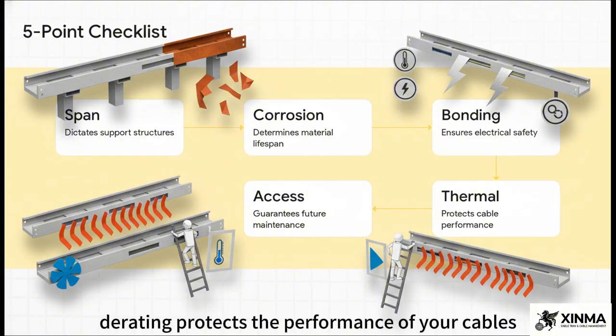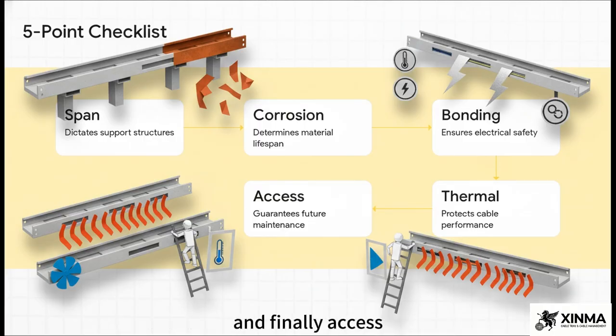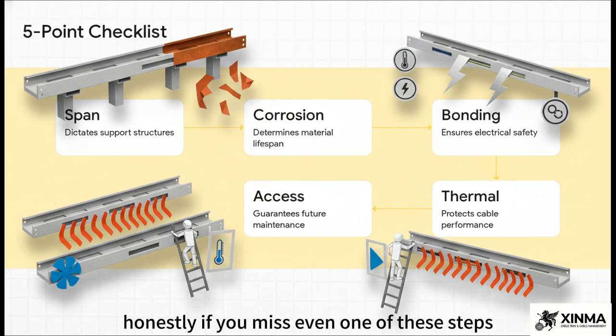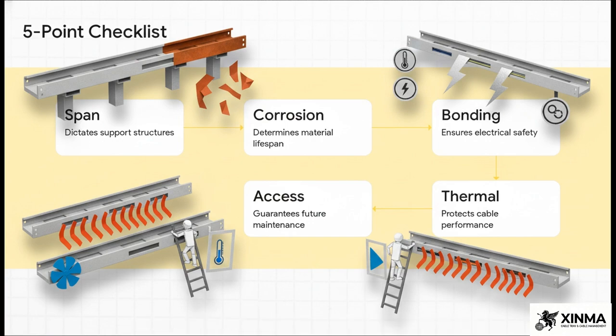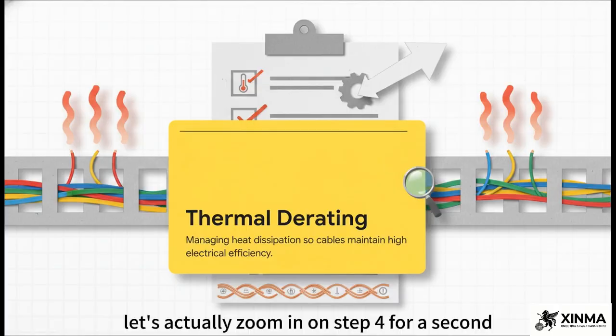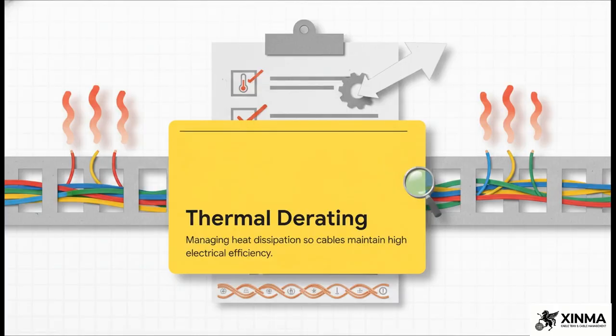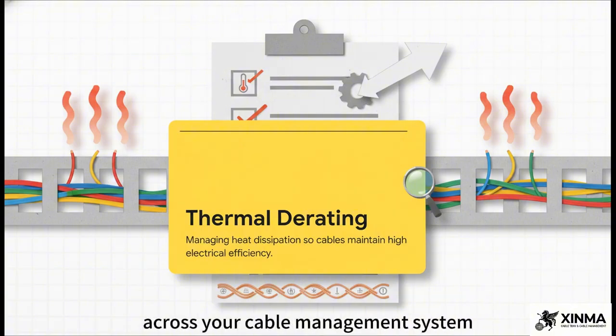Thermal derating protects the performance of your cables. And finally, access guarantees your maintenance teams aren't totally locked out of the system later down the road. Honestly, if you miss even one of these steps, the entire system becomes vulnerable. Let's zoom in on Step 4 for a second: thermal derating. This is such a crucial calculation for managing heat dissipation across your cable management system.